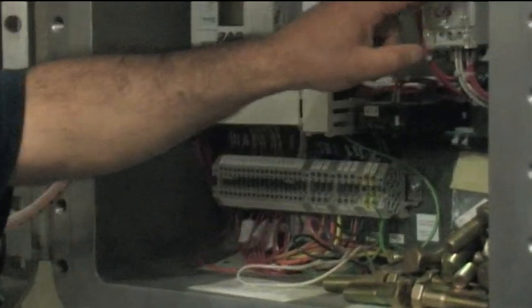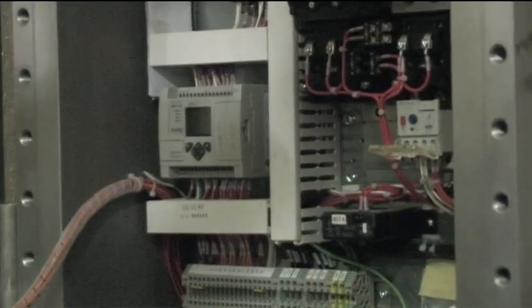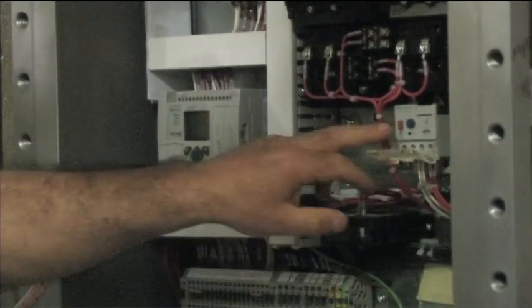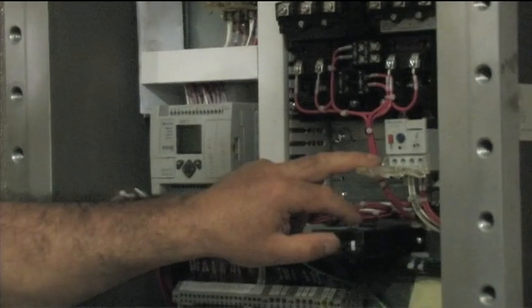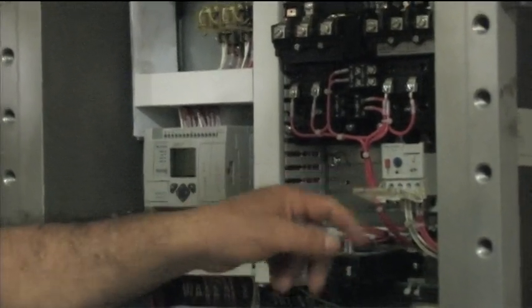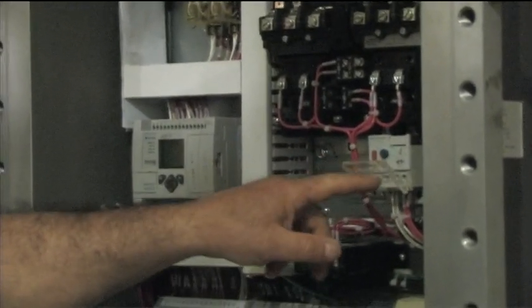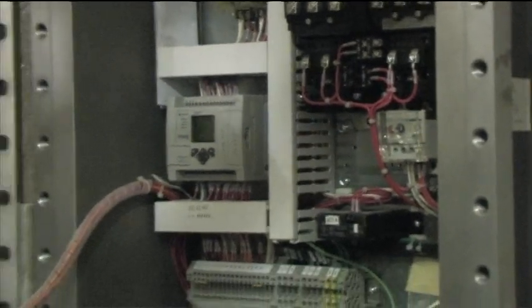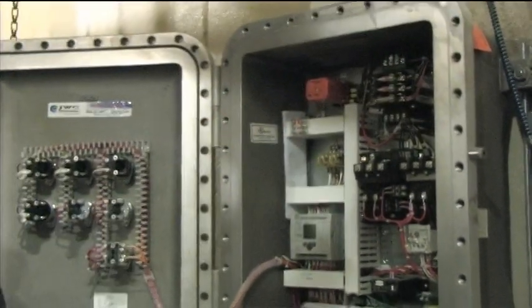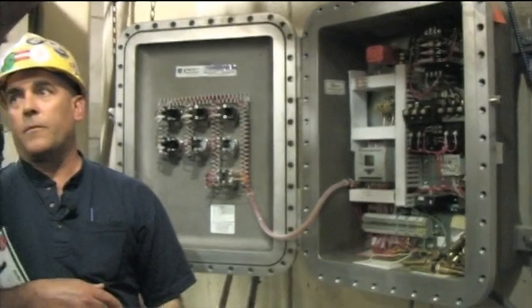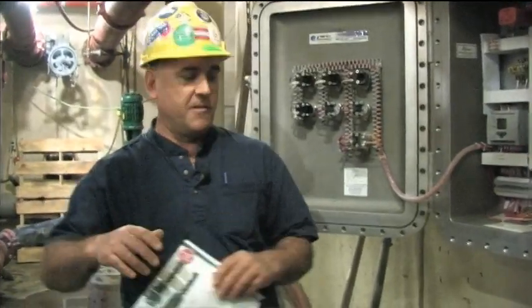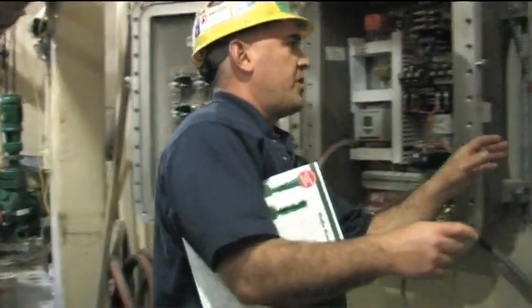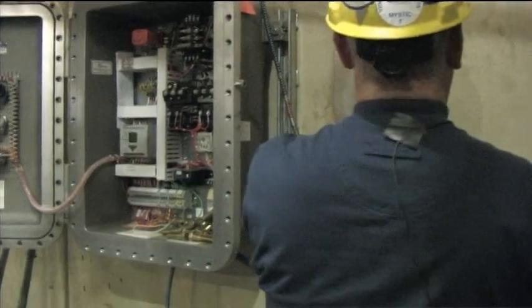Your motor overload here, reset. Full load amperage on the motor is 7 amps, so I already checked that, that's set correctly. And then you have your fuses up top here. If you have half a day, just open that up. Well, you better have your battery-operated drill, right? But I can simulate a jam from the panel here.